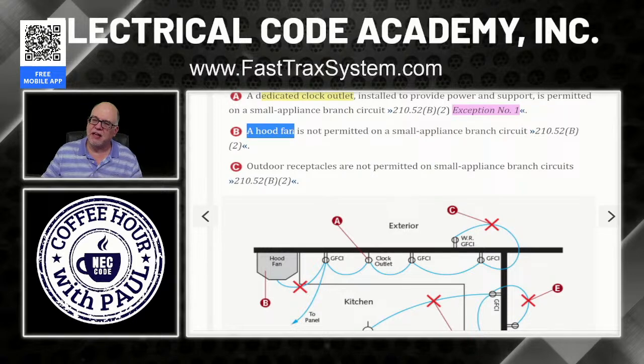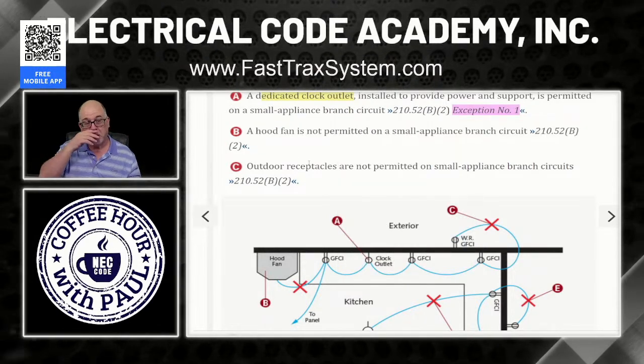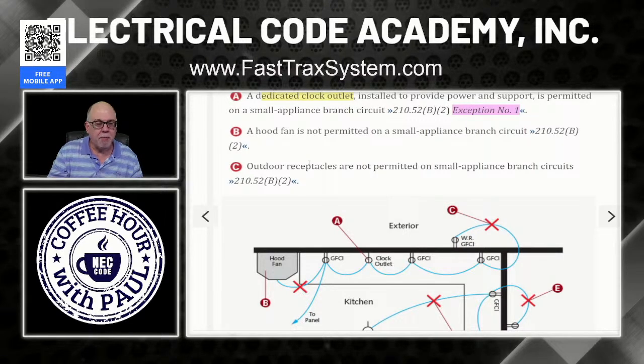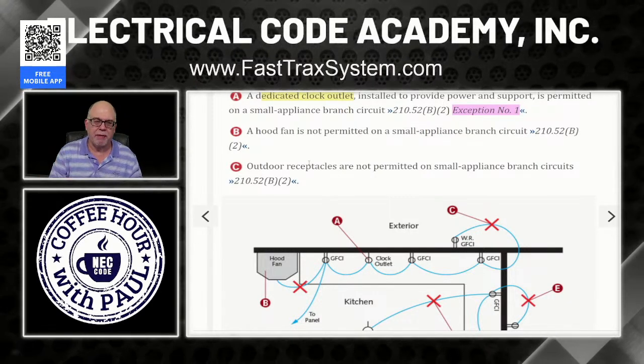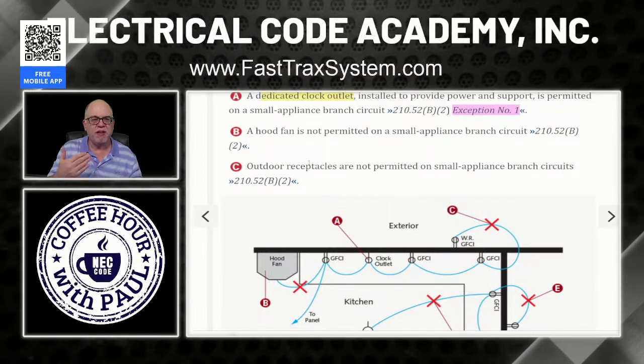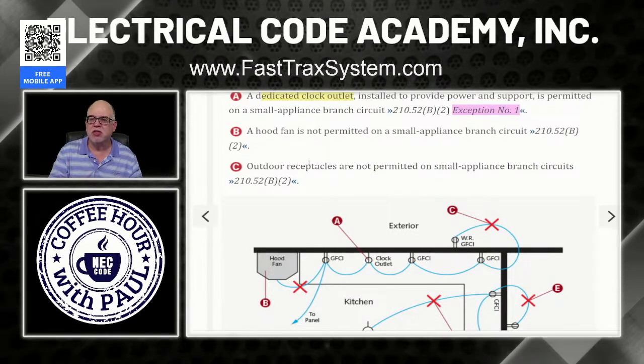A hood fan is not permitted on a small appliance branch circuit. 210.52(B)(2) gives us that direction and says it cannot be on a small appliance branch circuit. Also, just because we're talking about it, a microwave could not be on the small appliance branch circuit, okay? The manufacturers of that microwave are going to have in their instructions to run a dedicated or individual branch circuit to that microwave. Well, you have to follow their instructions, okay?